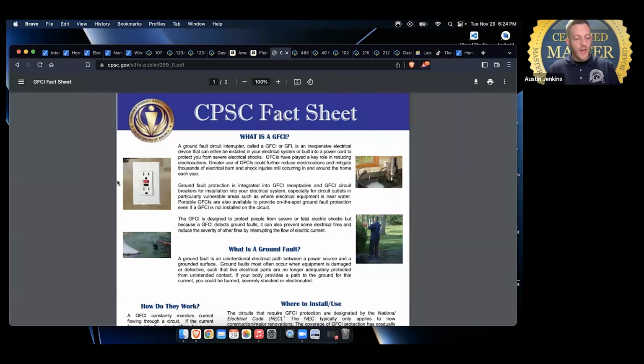That shows when specific areas were required by the National Electric Code to be installed. For instance, most kitchens require two dedicated GFCI circuits, assuming it's in the path of water. Really, you can think of path of water equals GFCI. If you have an area that could get wet, it needs to be protected either by a GFCI outlet or a GFCI circuit if it's downstream, which is one of the most common setups that I see in new construction. You can walk into a brand new house and it won't have any GFCI outlets in the kitchen, but all of those circuits are on GFCI breakers, which is perfectly fine because they're protected the exact same way.